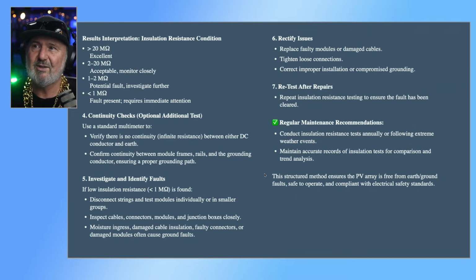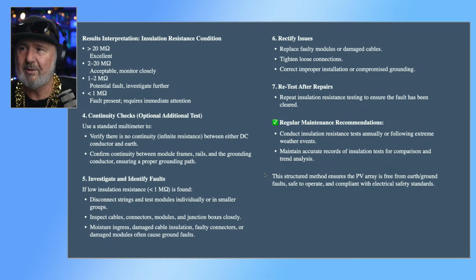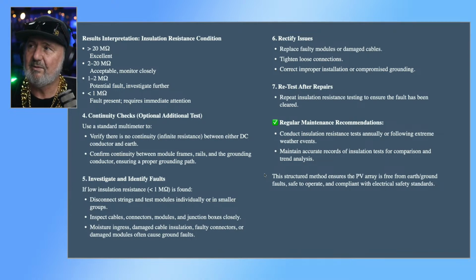What about the results? You can see the potential for failure if you get a relatively low reading, particularly if it changes when you spray water onto the system. Also do continuity checks between earth and the DC conductors, and make sure that all your module frame rails are properly earthed to less than 0.5 of an ohm, which is the requirement in 3000 for protective earthing. It's also the requirement for equipotential bonding in 5033. And there you go. So rectify the faults, tighten all loose connections.